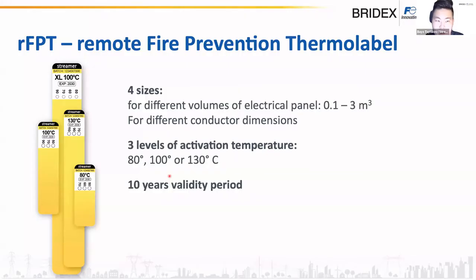Let's talk in more detail about each product. It will be short. The RFPT, or sticker with signal gas, comes in different sizes for different sizes of compartment, because every sticker has a different amount of signal gas inside. We have this one for a 100-liter compartment, and this big one is for a 3 cubic meter electrical panel. We have different activation temperatures: 80, 100, 130. The sticker for 100 degrees is the standard one. The others are for some specific projects. And every single sticker has a 10-year lifespan.